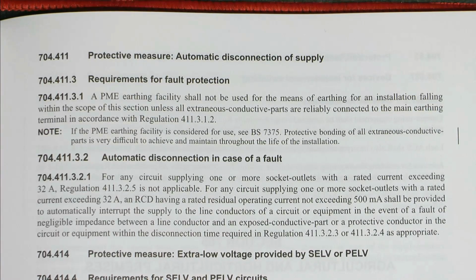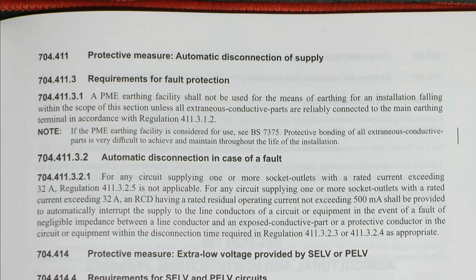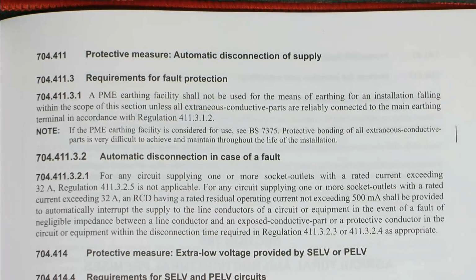That's basically what it said before. And then additionally, protective bonding of all extraneous conductive parts is very difficult to achieve and maintain throughout the life of the installation. So basically it's not recommending you should use that kind of method of protection on a construction site. And so it's just moved the note and has rewritten a bit of it.